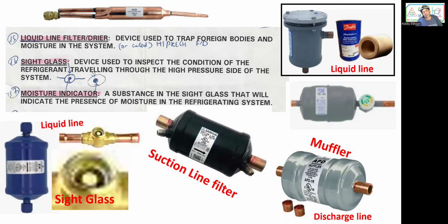Okay. And we also have the suction line filter. I included it with the filters. Suction line filter is just a filter. It's not a dryer, only a filter. And the suction line filter also has many reasons to use it. We try not to use it because we don't want restrictions on the suction line. It's mainly used if we have acid in the system, so it can pick up the acid for cleanup. And it has a place to check for pressure, because that's how we check if the filter is clogged, is the pressure before the filter.